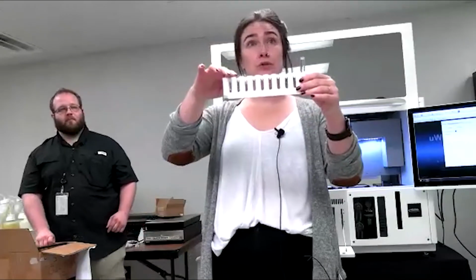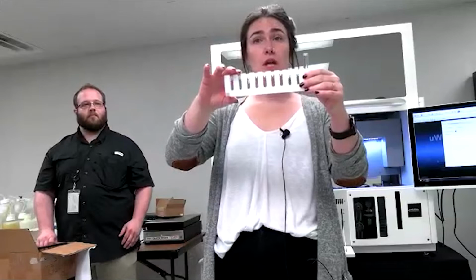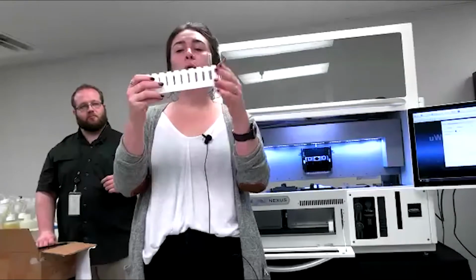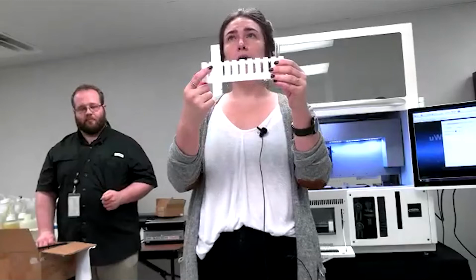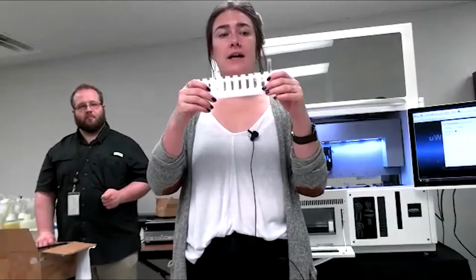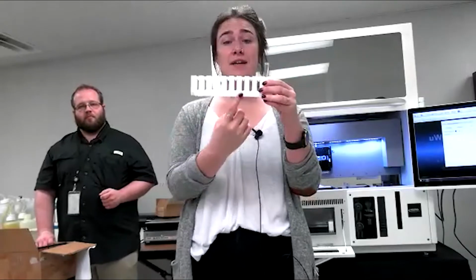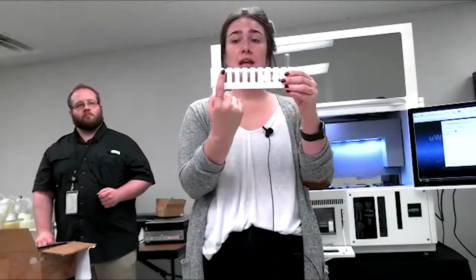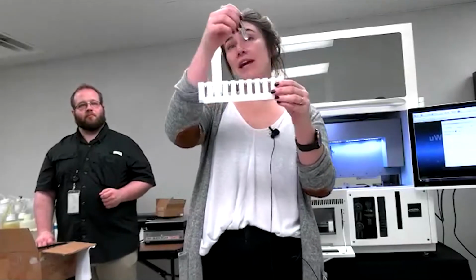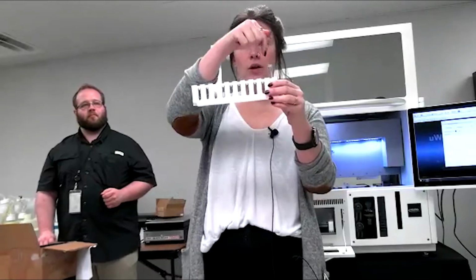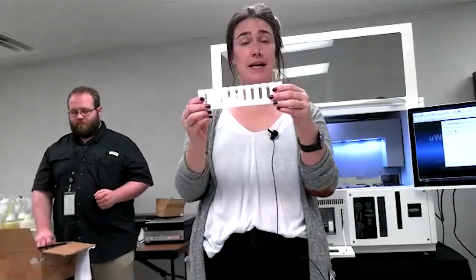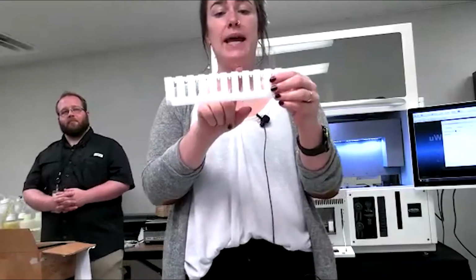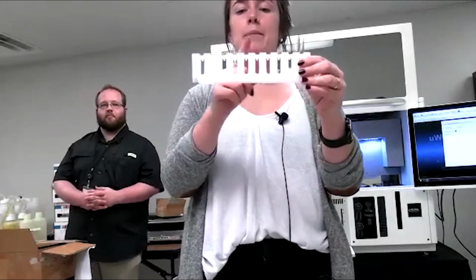I mean the remaining sample number. If the remaining sample number is not enough for the rack, oh, I see what you mean. So if your rack isn't full, yeah. So it will check every position up to the number that the test is set for. So in an IFE 9, it will go to each position and check for a sample. If you have a tube in it at all, it will bring the pipette down and try to aspirate a sample. However, if you leave it blank like this, it will skip over that.